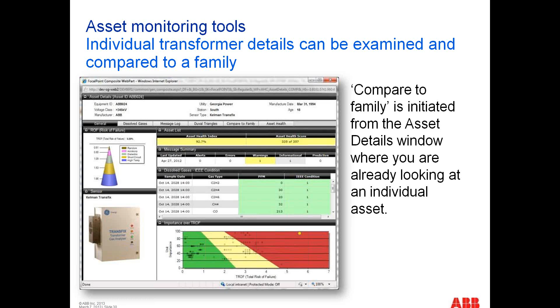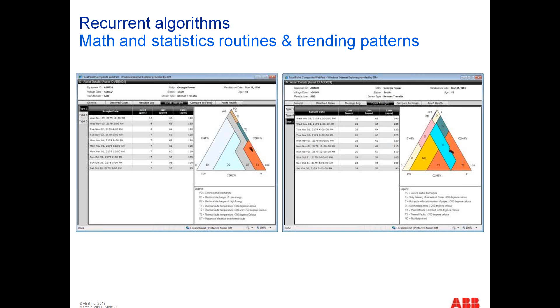We're using a lot of our own algorithms, as well as industry standard tools like the IEEE guides and the Duval triangle. In this case we've got type 1 and type 5, and you can see how that black dot is moving, with the most current reading being the biggest dot and the fainter or smaller dots showing where it's come from. This gives you an idea what's going on with your transformer once you spot a trend that's a little alarming, whether your actions are improving its condition, or whether you really need to react to what's going on.